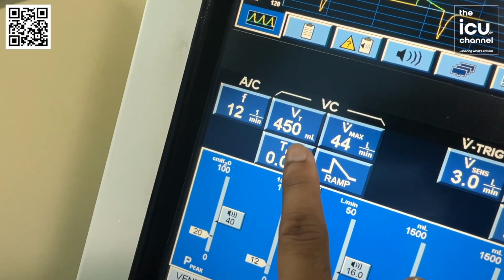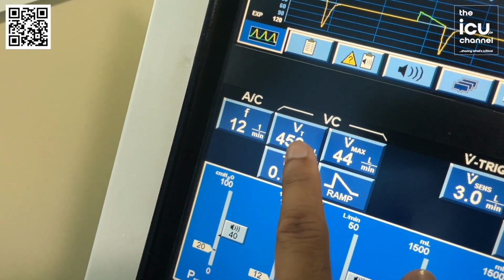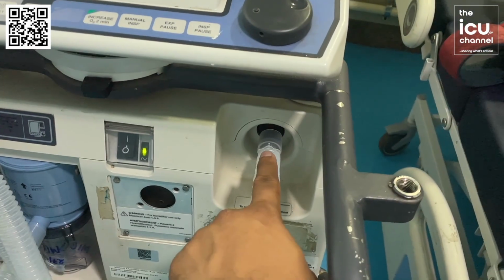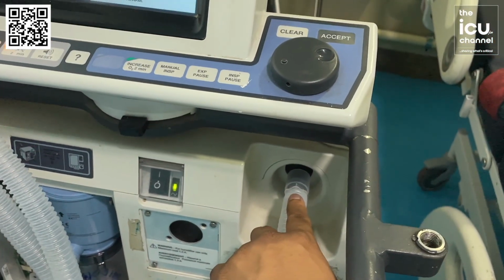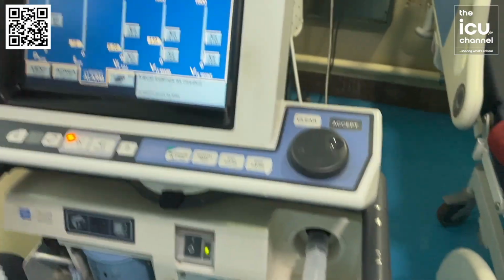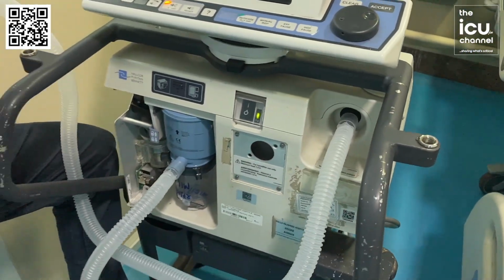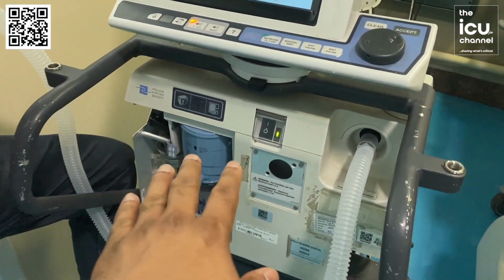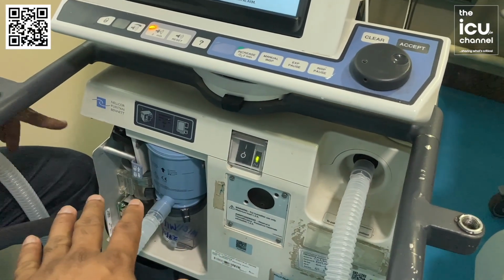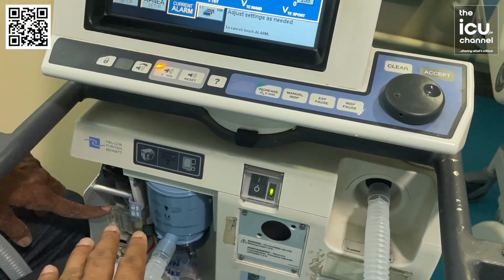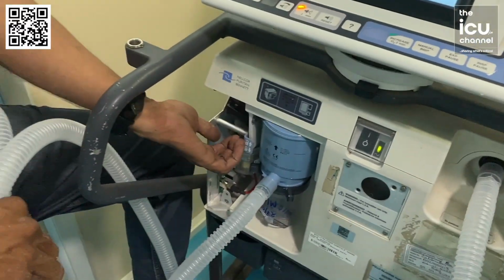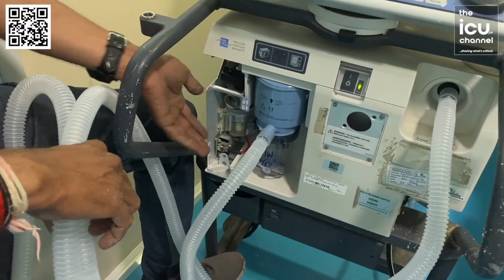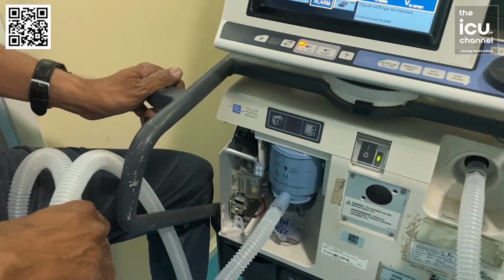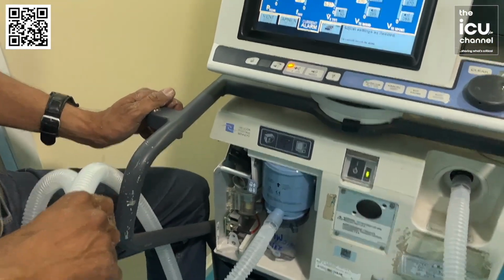That means the amount of tidal volume which we have set is coming out of this inspiratory limb, meaning it is delivering. Now this will go to the patient, and then the patient will send it back, to the filter, the expiratory flow valve, and the flow sensor. And now it will move out. It will move out in the environment.